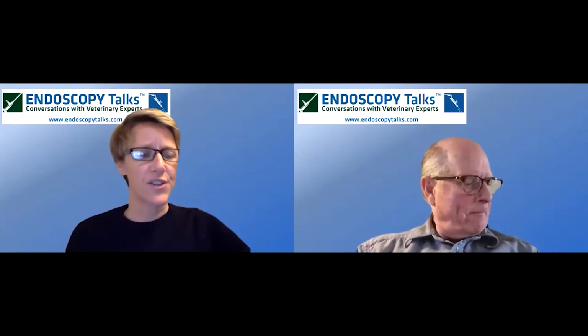Yeah, that's a very good question. So flexible endoscopes tend to be used for more tortuous pathways. So for instance, we've used that for tracheal bronchoscopy, where you need that flexibility to get into more tortuous pathways. You'd use a flexible endoscope for retroflex nasopharyngoscopy, so you need to have that nice bending over the top of the soft palate. You would also use the flexible endoscope for upper and lower gastrointestinal endoscopy, where you need to go through little bends and curves. So that's typically what you would use that for.